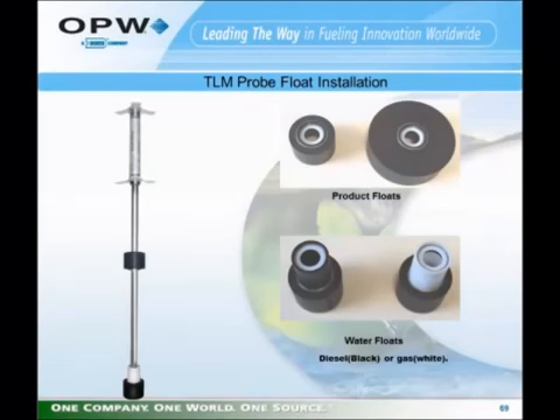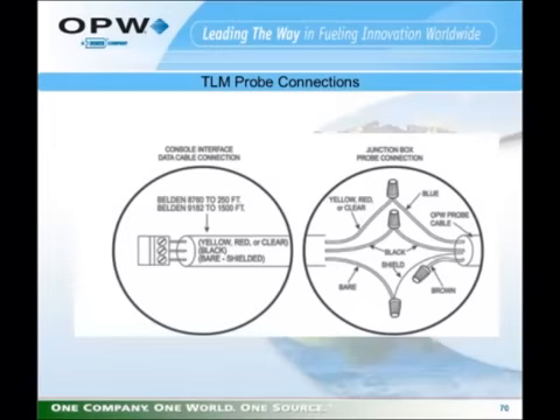The probe float installation, we've covered this earlier. We show you again illustrations of the floats, keeping in mind that the 4-inch product float is no longer available. TLM probe connections. The probe cable that we are now supplying is a blue intrinsic safe cable with 3 wires and a shield in that cable.